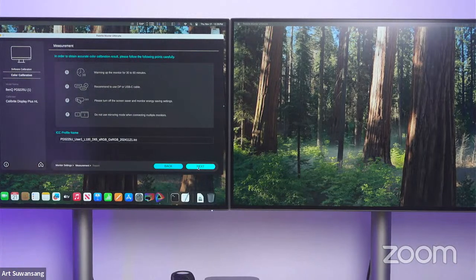And it says that we always want to leave our display on for at least 30 to 60 minutes. My magic rule of thumb is around 15 to 20 gets the display to warm up enough. And it doesn't really matter whether you have a brand new display or this display is older. Now, they also recommend that you use either DisplayPort or USB-C. Here's the thing. If you use HDMI, can you run a calibration with it? Yes, that's not a problem. However, I would just run a calibration and check whether it passes the validation or not. If it doesn't, you might want to look at using a different source.